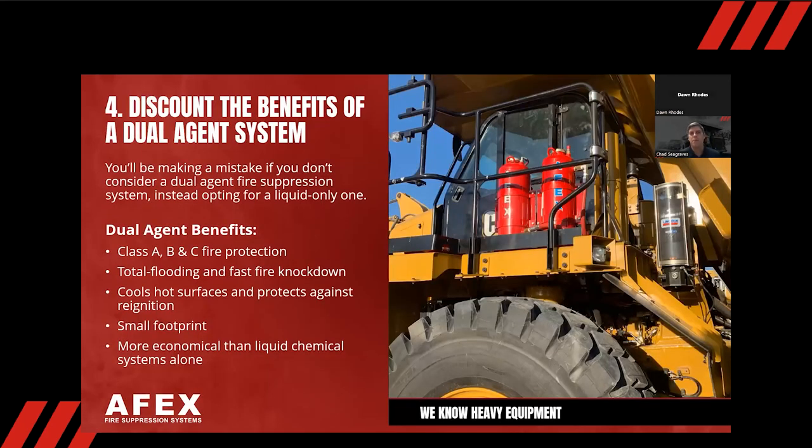Number four: discounting the benefits of a dual agent system. Here at AFEX, we use both liquid and dry chemical. Liquid chemical is a great product, and a lot of our competition uses liquid-only systems. But we — along with the NFPA — believe dual agent is necessary on larger machines. The NFPA states that if you've got more than 150 gallons of diesel fuel or hydraulic fluid, you need a dual agent system. Dual agent is also required on all hydraulic shovels per the NFPA.